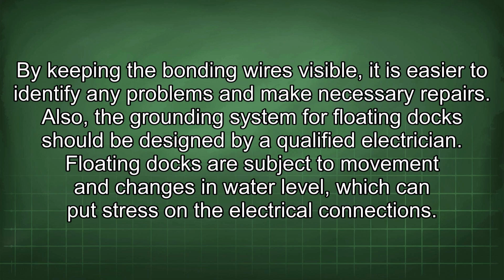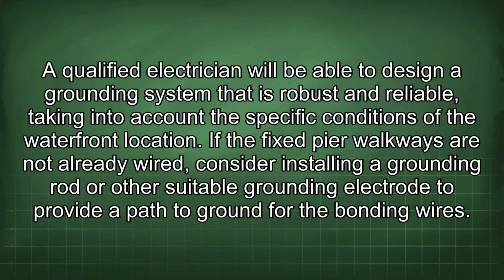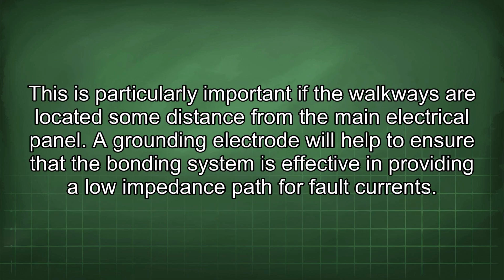Floating docks are subject to movement and changes in water level, which can put stress on the electrical connections. A qualified electrician will be able to design a grounding system that is robust and reliable, taking into account the specific conditions of the waterfront location. If the fixed pier walkways are not already wired, consider installing a grounding rod or other suitable grounding electrode to provide a path to ground for the bonding wires. This is particularly important if the walkways are located some distance from the main electrical panel.